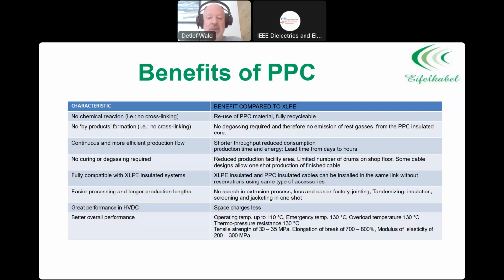Tandem extrusion, for medium voltage at least, lets you make the insulation — meaning the cable core, the screening, and the jacketing — in one shot. The space charges for HVDC in polypropylene are lower, and I'll come back to that later. The thermal performance allows an operating temperature up to 110 degrees, emergency temperature like XLPE up to 130, overload temperature also in that area, and you still have very good mechanical properties.